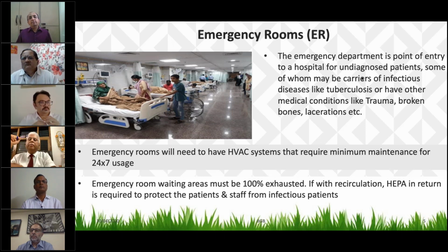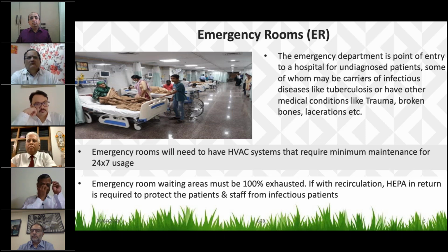Sir, the current emergency rooms generally have a roof air ducting system. So do we need to go in for a change and install split ACs? Or might the split ACs need a definitive change of the current filter? What we are recommending is that in the emergency room you should have a 100% exhaust, so the question of recirculation should not be there. That might give you a far better result. But if you don't have this 100% exhaust available, and you've got these existing high walls and cassettes, then so be it. Then you have to have negative pressure and exhaust as much air as possible, and replenish it with a certain amount of fresh air.